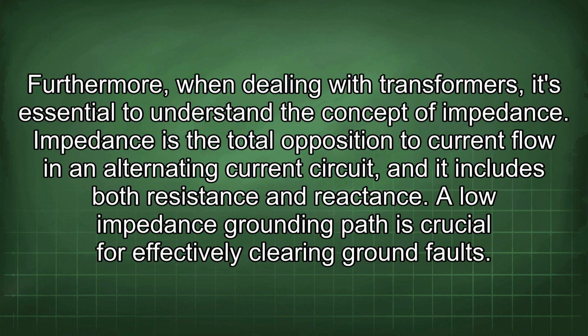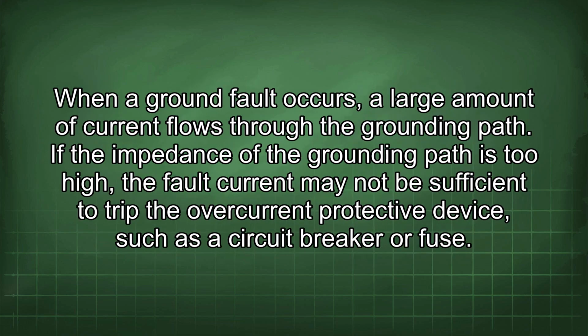Furthermore, when dealing with transformers, it's essential to understand the concept of impedance. Impedance is the total opposition to current flow in an alternating current circuit, and it includes both resistance and reactance. A low impedance grounding path is crucial for effectively clearing ground faults. When a ground fault occurs, a large amount of current flows through the grounding path. If the impedance of the grounding path is too high, the fault current may not be sufficient to trip the overcurrent protective device, such as a circuit breaker or fuse.